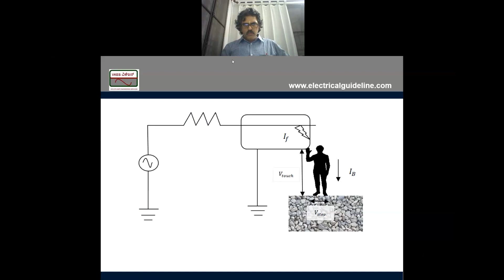How do we reduce the touch and step potential of a substation? First, we have to determine the touch and step potential which a person can tolerate. Then we have to compare it with the actual value attained at this site. Now, how do we reduce? Let's say the allowed value is 300 and the actual value at the substation is 400. So what we have to do is bring this 400 down to below 300. How do we do that? By design.